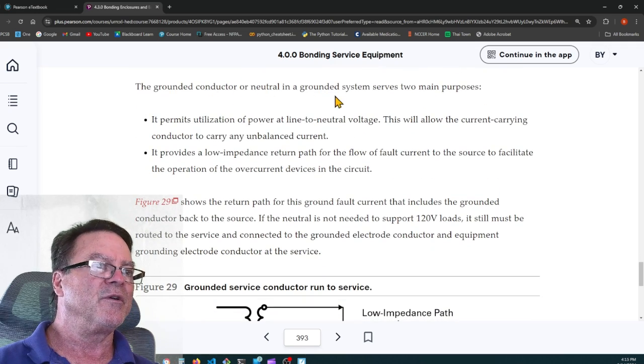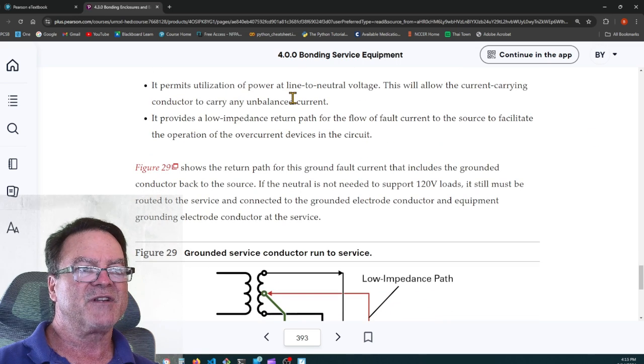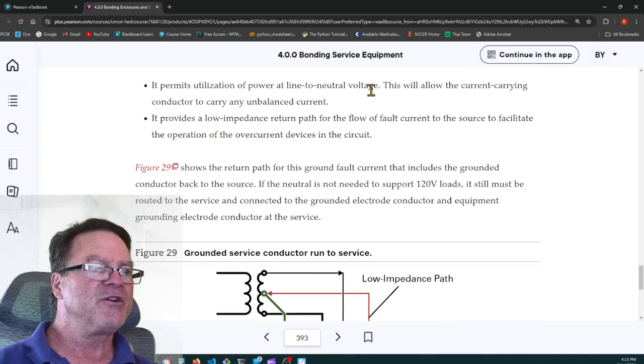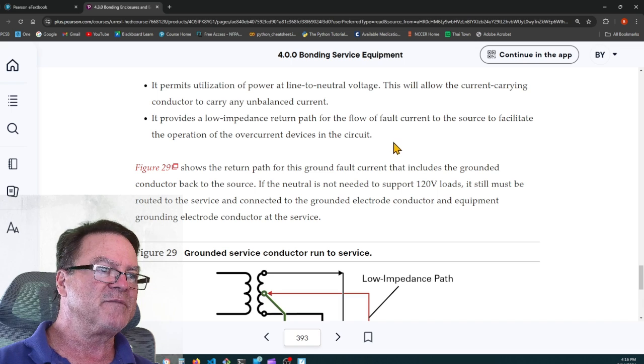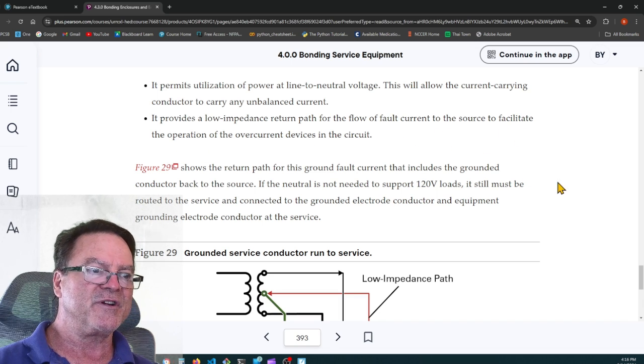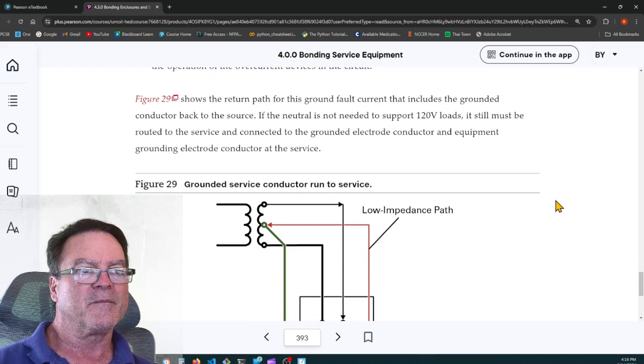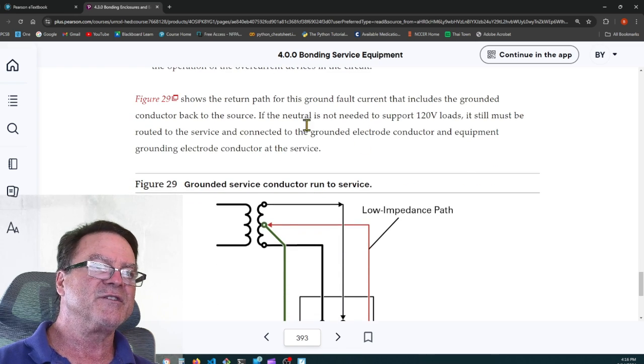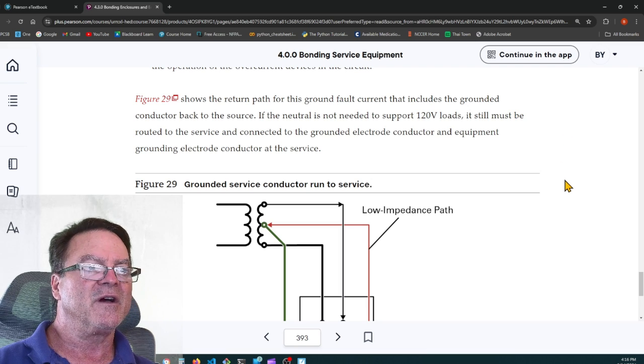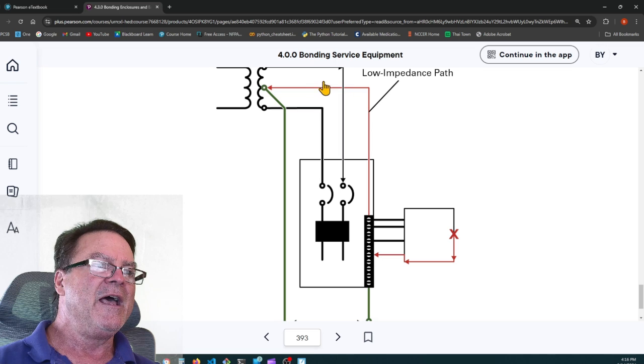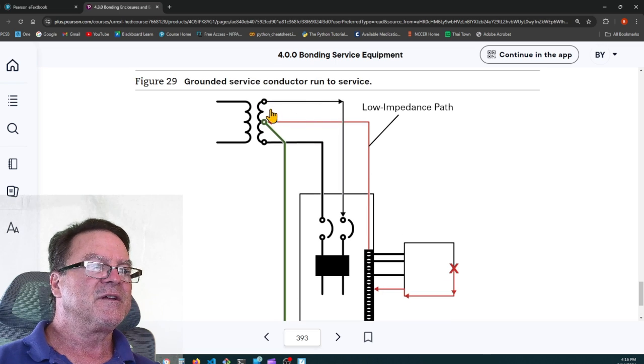A grounded conductor or neutral in a grounded system serves two main purposes. It permits utilization of power at line to neutral voltages. This will allow the current carrying conductors to carry any unbalanced current, and it also provides a low impedance return path for the flow of fault current to the source to facilitate the operation of the overcurrent devices in the circuit. So, figure 29 shows the return path for this ground fault current that includes the grounded conductor back to the source.